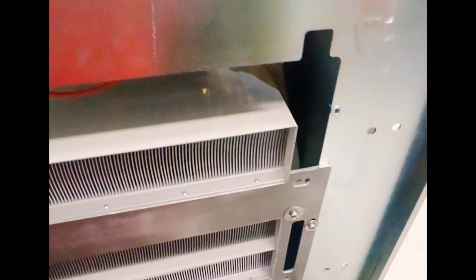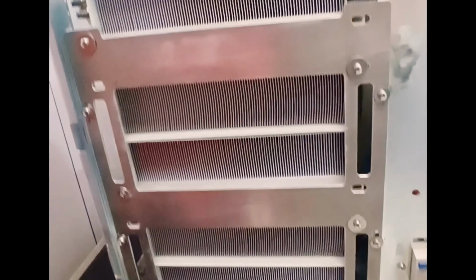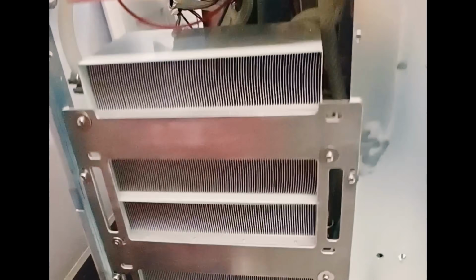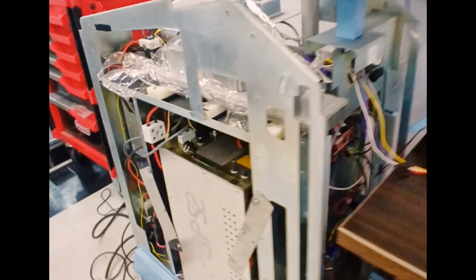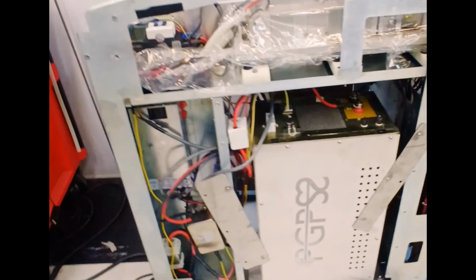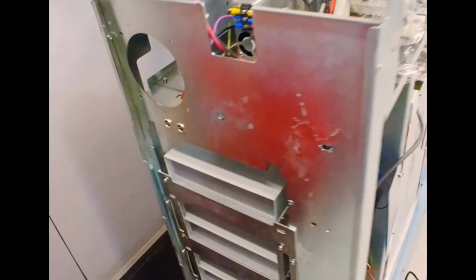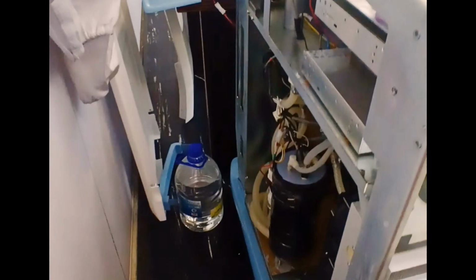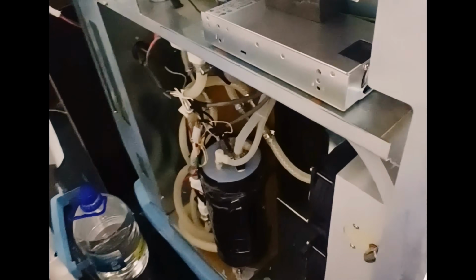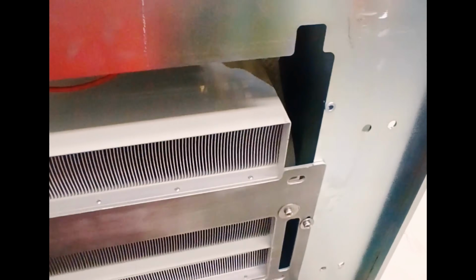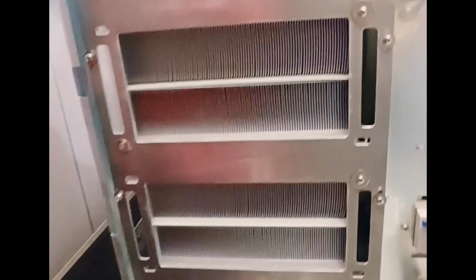required for different devices. For example, here I connected 3 of these chillers in series for this laser device and kept the water temperature constant at 22 degrees with a PID temperature control module. These Peltier chillers are mostly used when the temperature of a device needs to be controlled with high accuracy, for example, 0.05 degrees Celsius, or in compact systems that require a chiller with not very high cooling capacity.